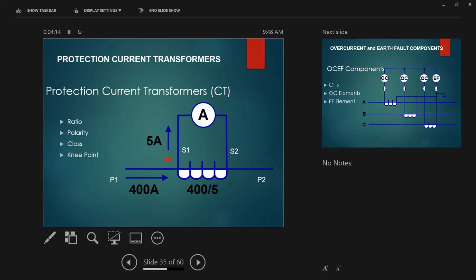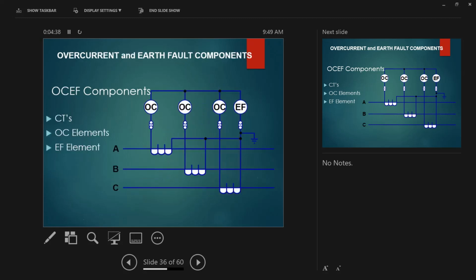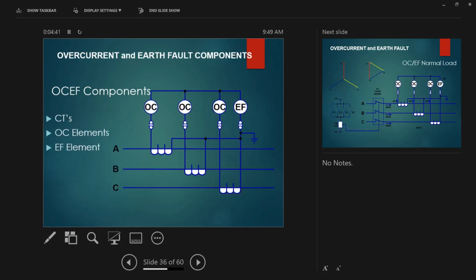So this is the older generation, where the CT secondary is 5 amps. So of course, if 400 amps is flowing in the line, the secondary is automatically 5. If this is 200 amps, the secondary will be half as well, 2.5 amps. So that's a simple ratio and proportion. So you see the overcurrent and earth fault, composed of 3-phase CT, overcurrent elements and earth fault elements. So you have that there.